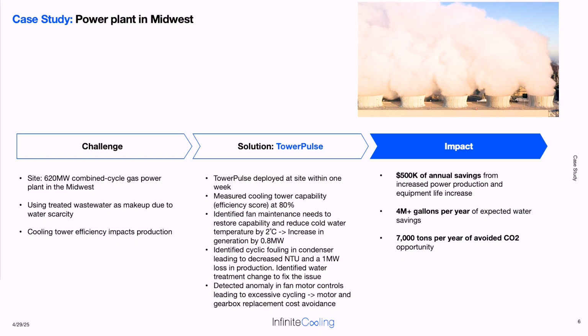It took just a few days to install because these are wireless sensors that are externally mounted. We immediately found out that their cooling tower was operating only at 80% efficiency, and our algorithms were able to determine the causes of that drop in efficiency, which in this case was basically some airflow issues where they needed maintenance on their fans.